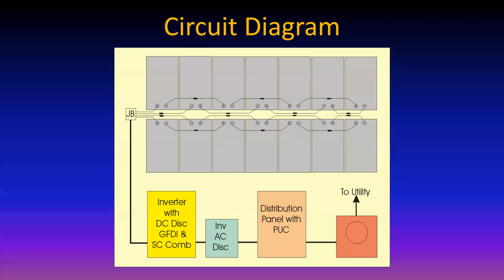A note on that circuit breaker: if you turn that circuit breaker off, the PV system thinks the utility is dead, so it shuts off. Therefore, the load side of that breaker, which is where you're feeding the PV in, has no voltage on it anymore if it's turned off. And from the point of utility connection to the utility. And of course, you can always do line side taps or load side taps, following all the tap rules, if you don't have room in the distribution panel for your point of utility connection.